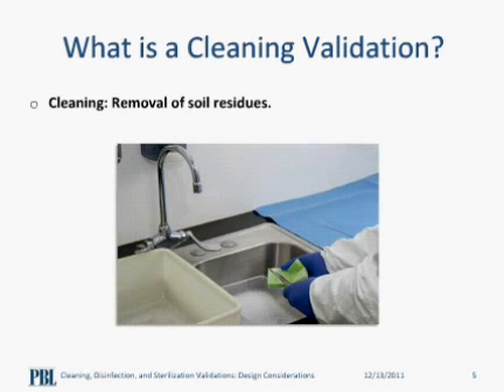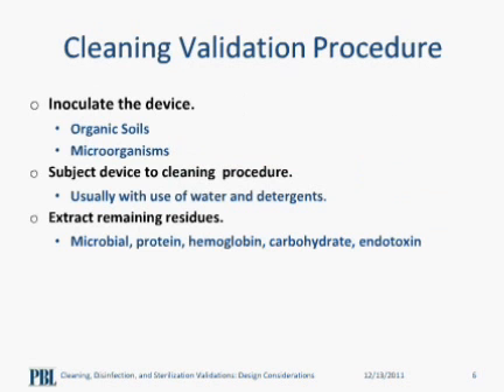Well, let's break it down. First, what is a cleaning validation? As a reminder, cleaning is defined as the removal of soil residues, whether organic, inorganic, or biological. And we validate a cleaning procedure by first inoculating the device with representative organic soils and microorganisms at the most challenging locations to simulate the worst-case scenario. Organic soil may consist of anything that would contaminate the device during clinical use, and the same goes for the inoculation of microorganisms. We inoculate microorganisms representative of the intended environment of your device.